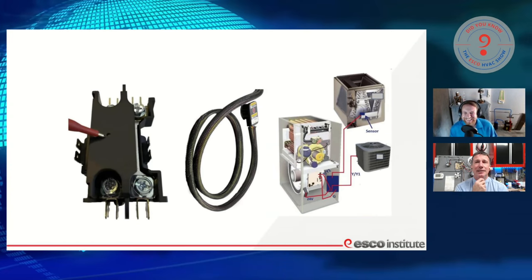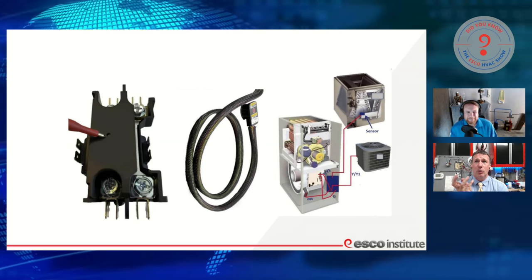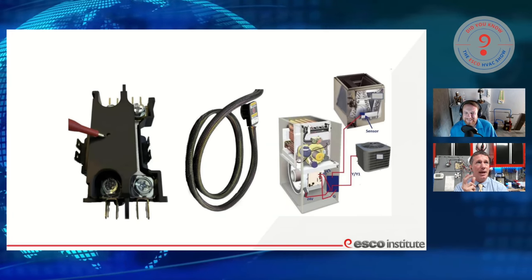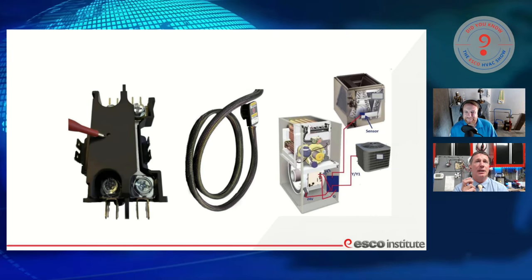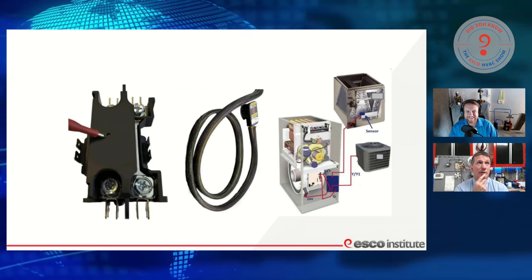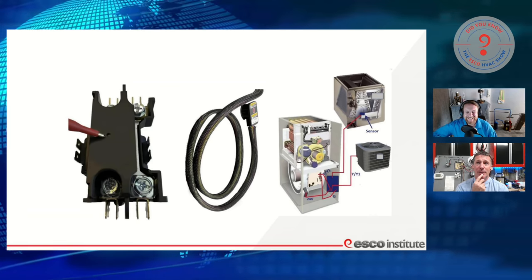I think we have — we've seen enclosed contactors for a very long time. Not a lot of manufacturers have been using them on residential equipment, but they look at it and go, well, here's an easy way we can reduce the potential for sparks off from our contacts. Let's just cover them. So we're going to see if your system has a contactor, it's just going to now be an enclosed contactor. And let's think about some other high energy ignition points — anyone ever seen terminals blow off from a compressor? More than I would like to.